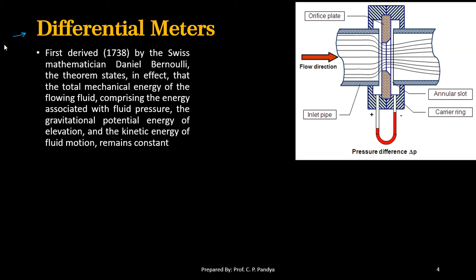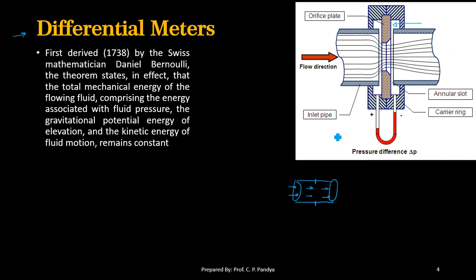Differential meters operate on the principle that if we have a pipe with fluid flowing inside it, and we put any plate inside that pipe which acts as an obstruction to the flow, then it creates a differential pressure. On one side the pressure will be P1, and on the other side of the plate the pressure will be P2. The difference between P1 and P2 is proportional to the magnitude of flow, whether we are measuring flow velocity, quantity, or volumetric rate.